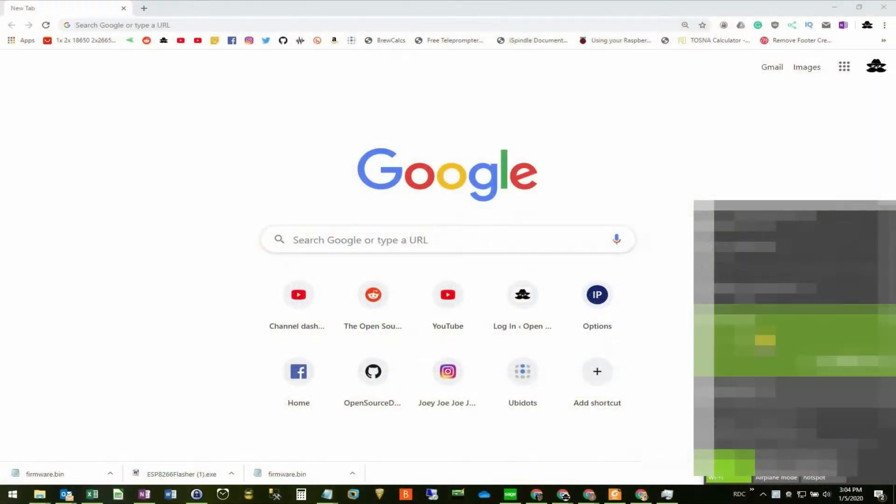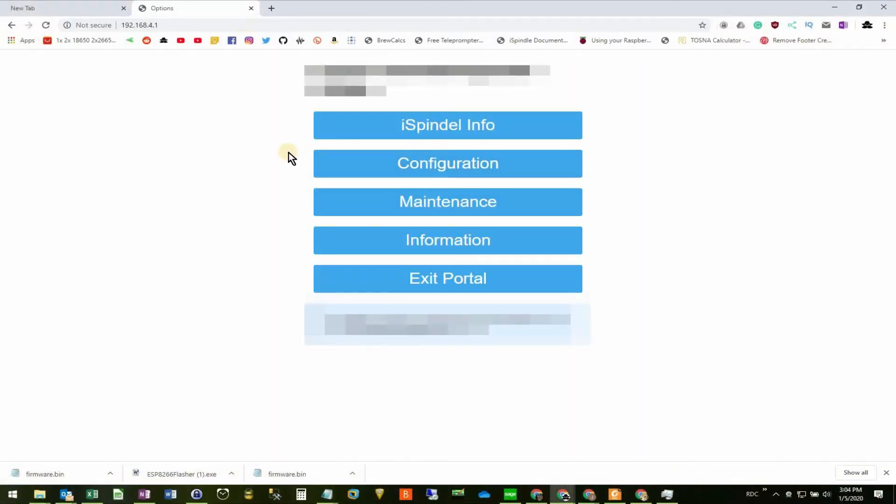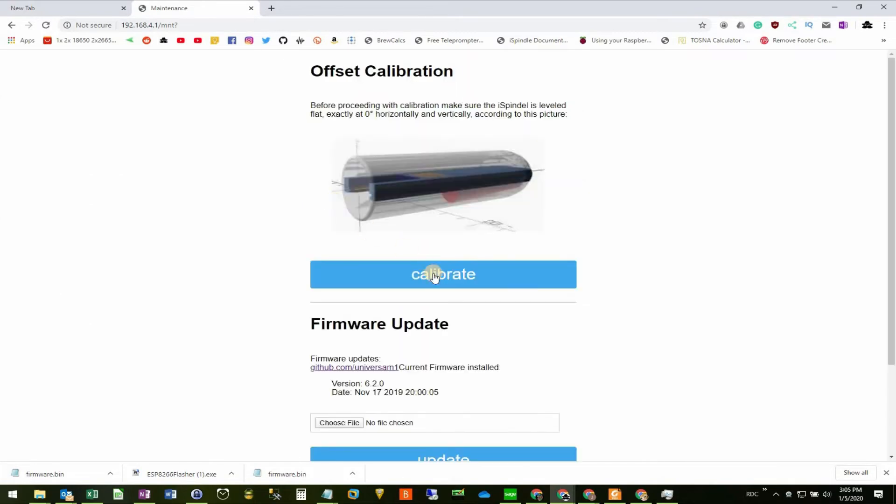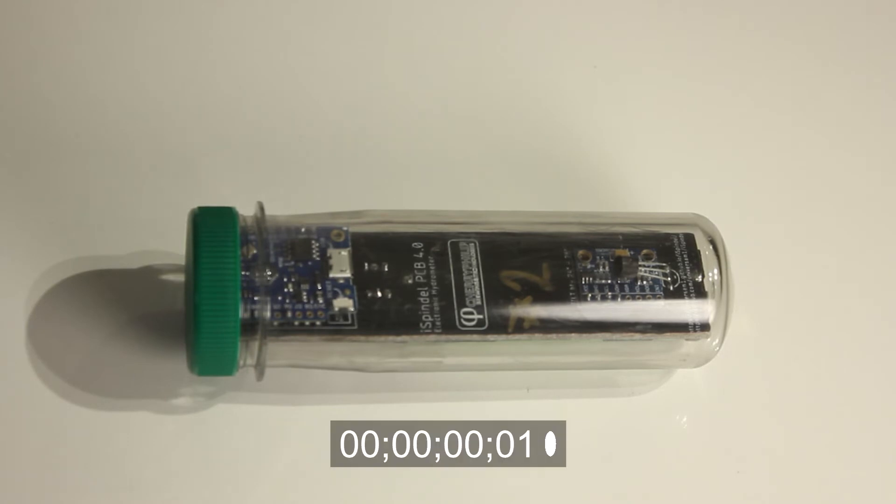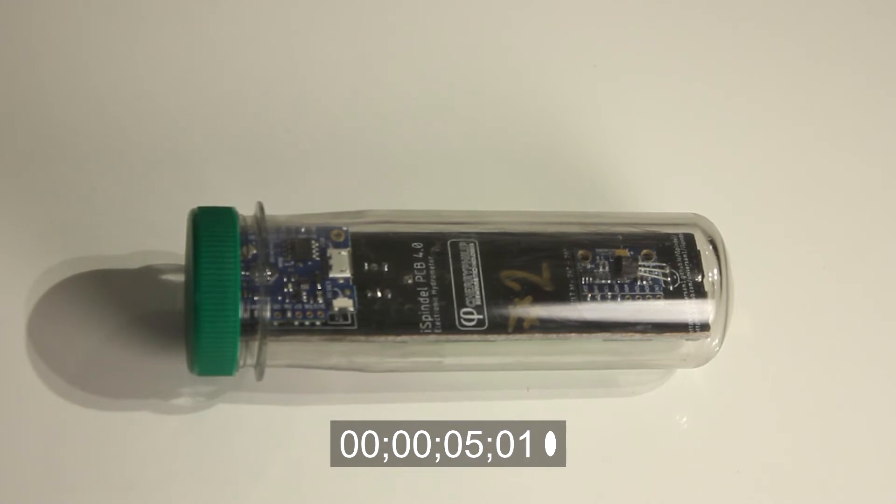Do the whole connection thing. Come back to the configuration page. Go to maintenance and calibrate. Notice that the new firmware calibration only takes 5 seconds to complete. And that is a huge improvement over the 2 minutes that it previously was.